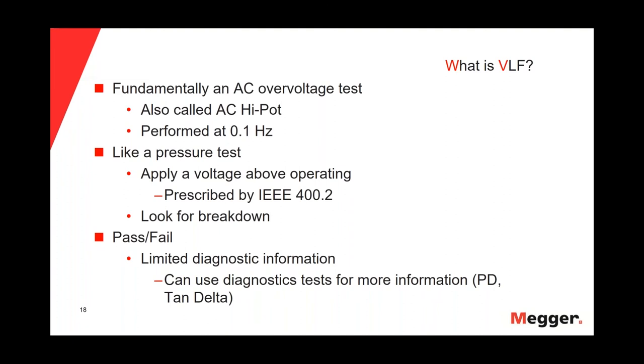If we are looking for the aging conditions of the insulation, or if we are looking for workmanship issues in the splices or terminations, then we need to use the tan delta or the partial discharge test. The VLF test is only a go/no-go test.